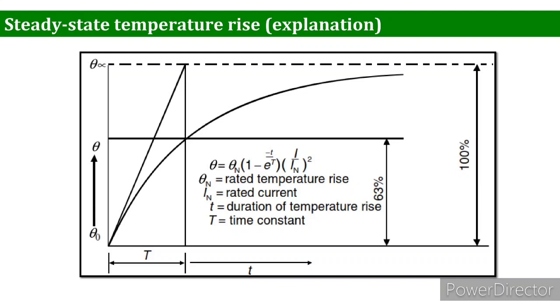Since a motor is not a homogeneous mass, heat is dissipated in several stages. So the temperature rise and fall take place according to a series of partial time constants, which you can see from the figure. We have divided its angle and the time, where capital T is the time constant, small t is representing the duration of temperature rise, In is the rated current, and theta n is the rated temperature rise. As I mentioned earlier, it will rise exponentially.